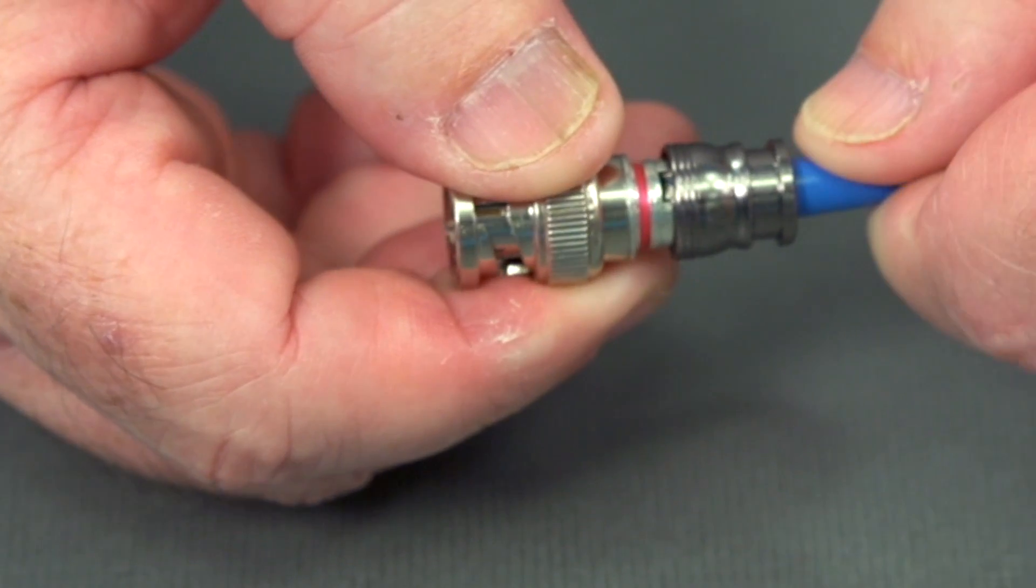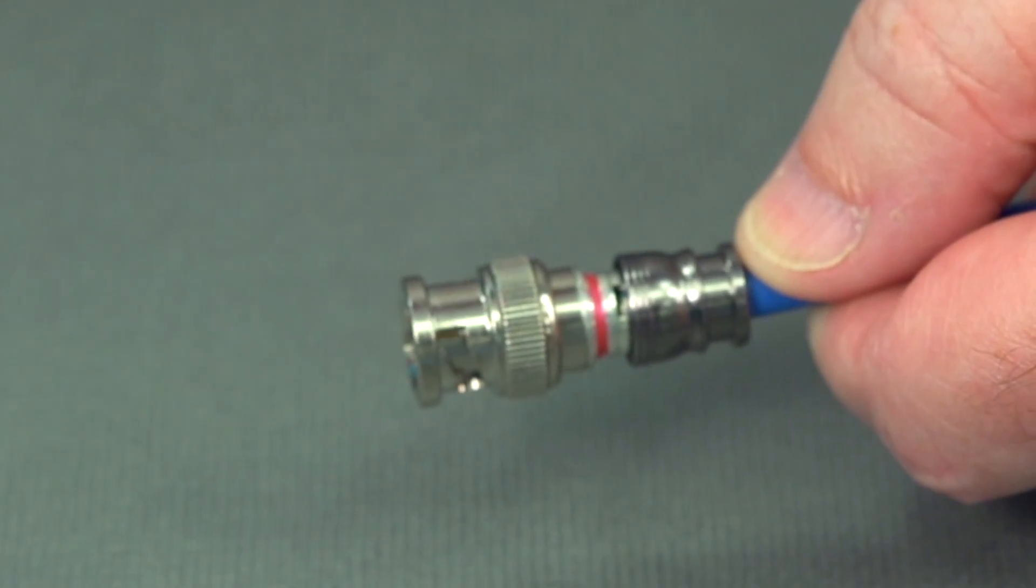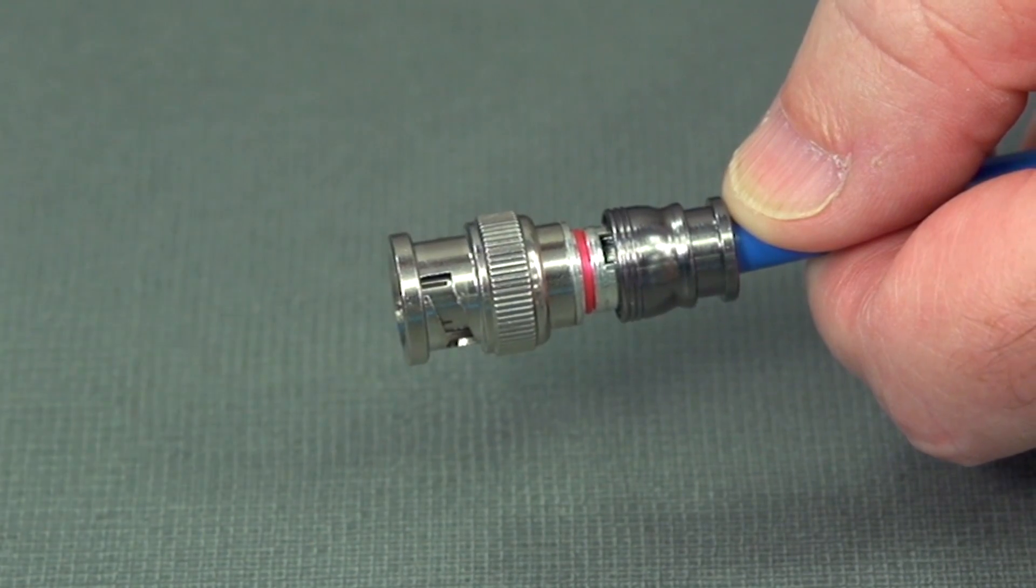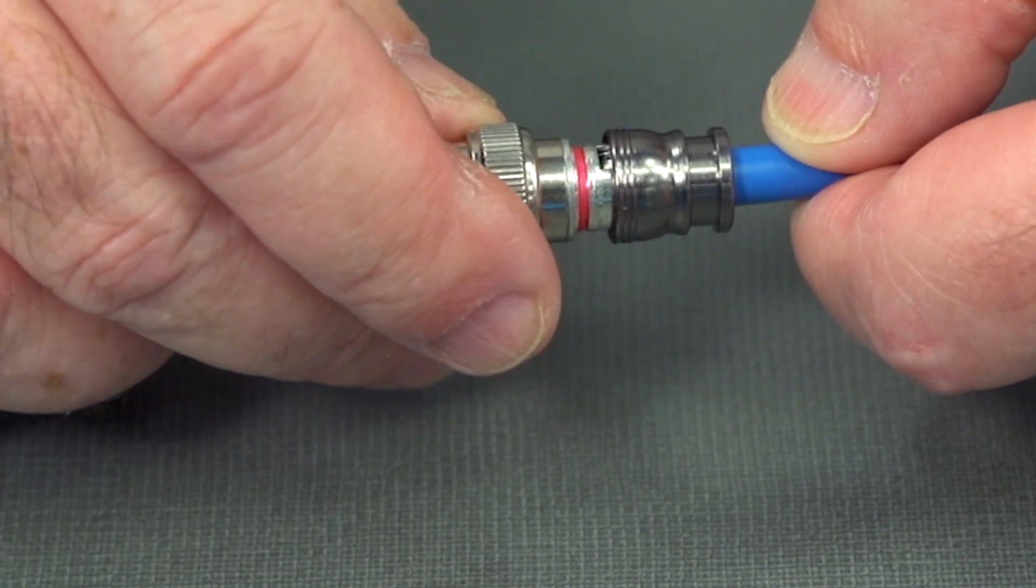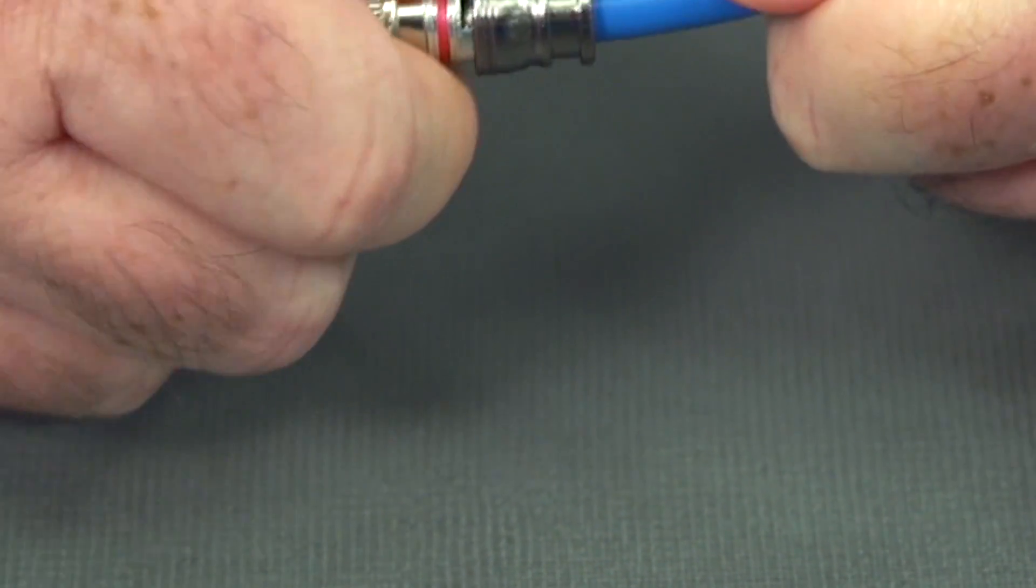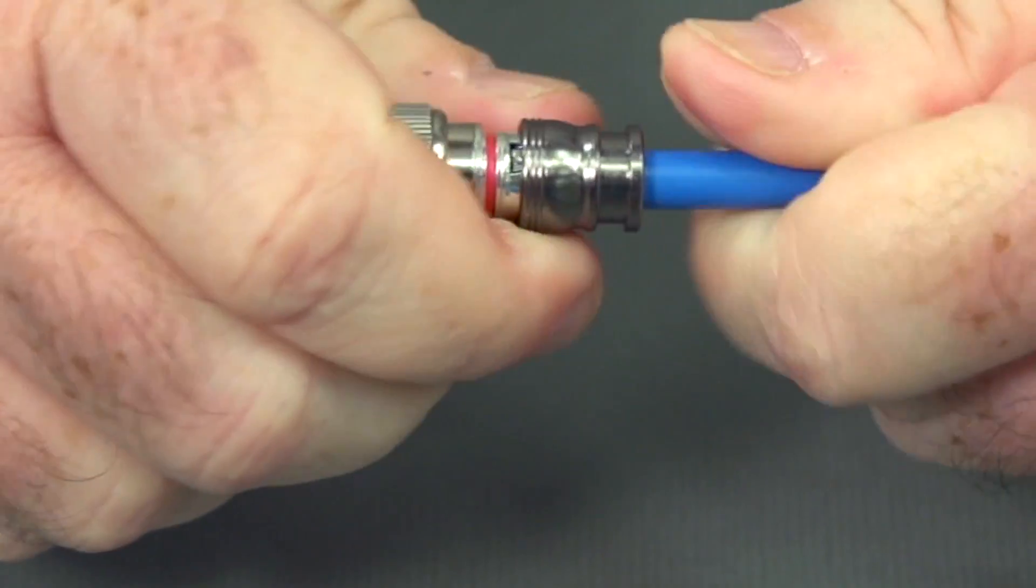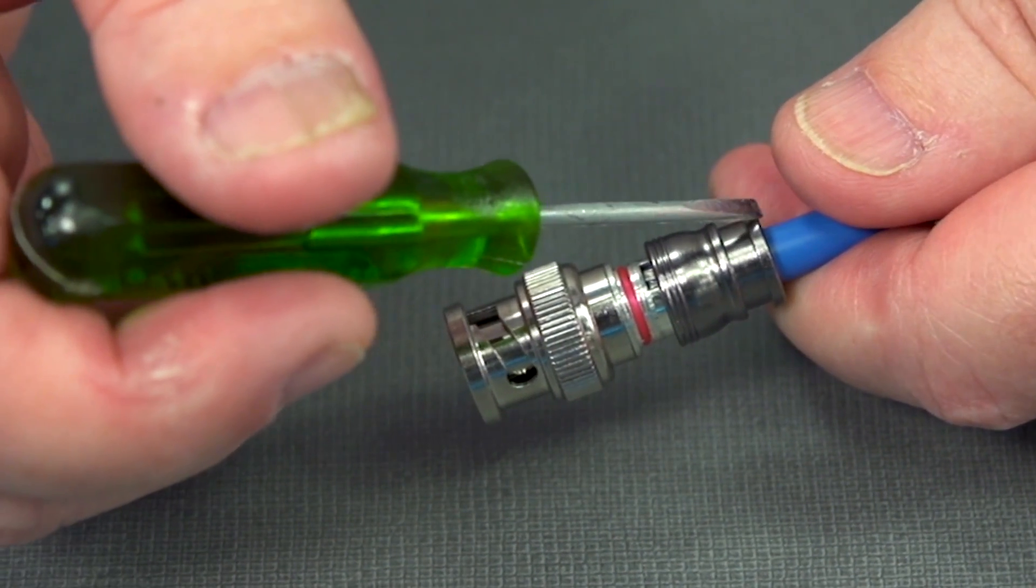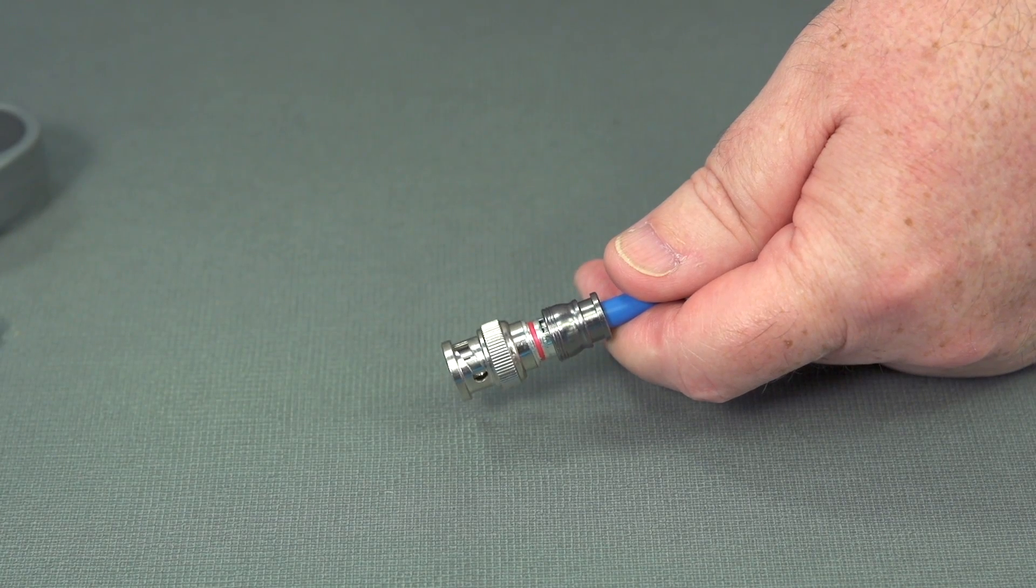Again, you can see that there's an inspection hole. So we should be able to see our shield inside the inspection hole. Let's give it a little bit more. There we go. So you can see the shield inside the inspection hole. That way we know that we pushed the cable far enough into the connector to make a good connection.